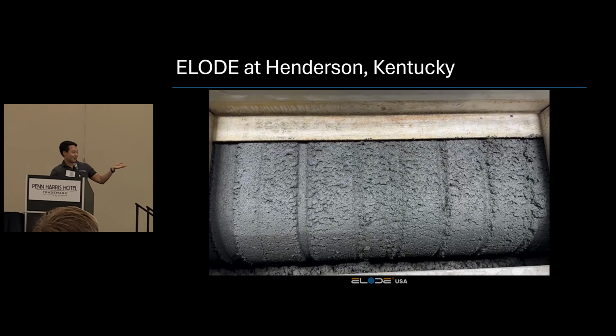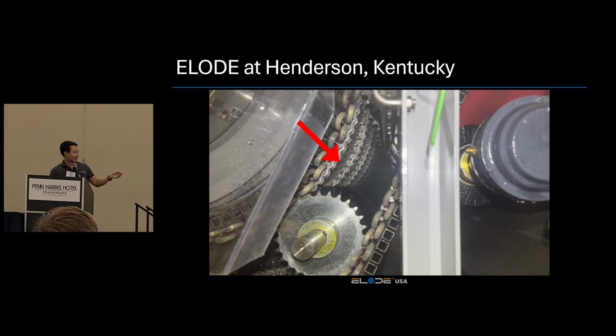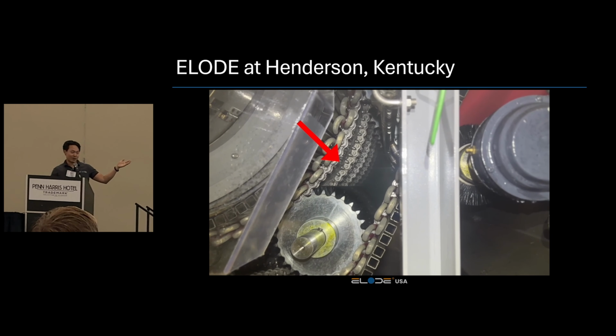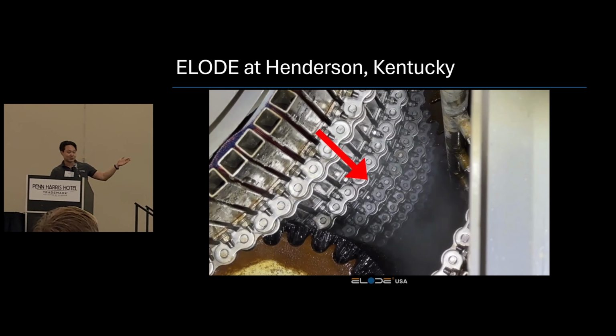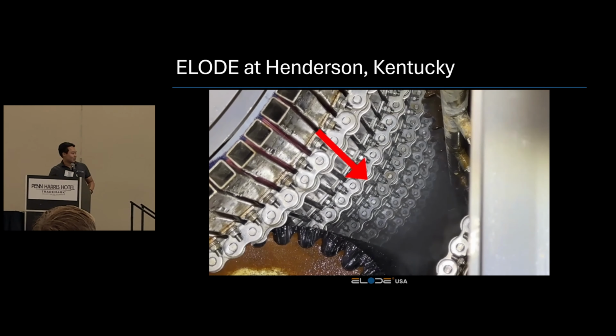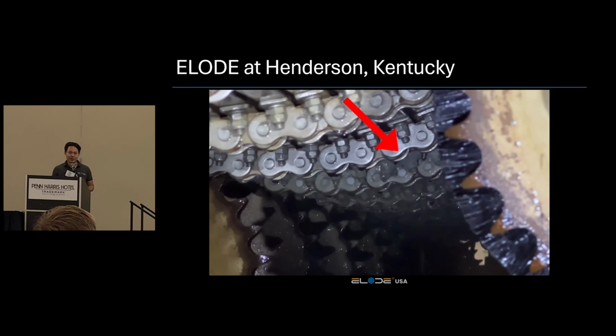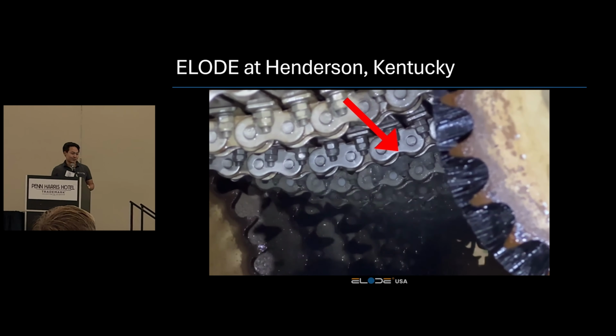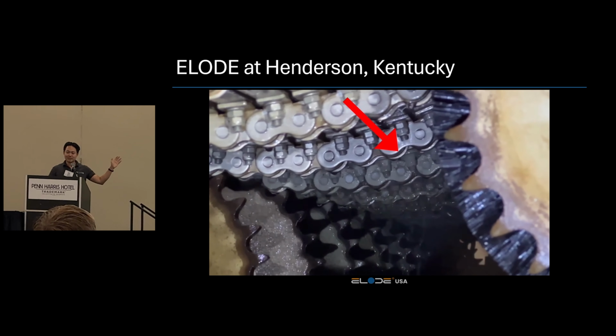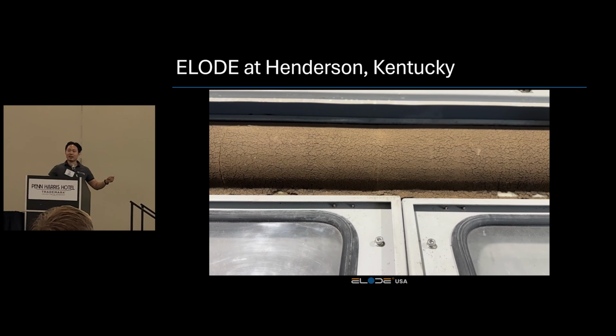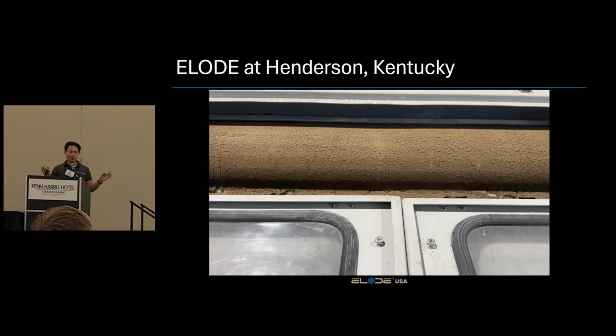That was the biosolids getting fed into the Elode, and here it is in the dehydration zone. Here's the electroosmosis in action. You can see the water instantly separating out of the solids and through the filter belt. Remember, that's all water you don't have to boil into steam. That's why Elode is able to get away with such a small footprint and not require so many additional components.